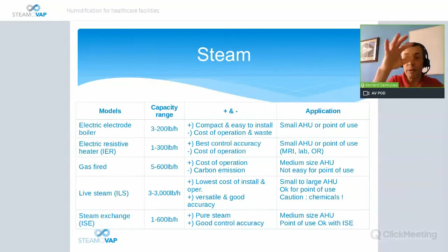But if you use a live steam humidifier at the point of use, it will be, let's say, one steam manifold, one ramp with a small valve, and then you can go to very low capacity, say 10, 30, 50 pounds. And then you can use it on the bigger air handling unit, feeding the whole hospital, at 3,000. That's a limit that we have placed, but you can go over 3,000 as long as you add pipes, nozzles and a larger valve. So it's probably the lowest cost of install and operation, very versatile, with very good accuracy. But caution, the chemicals have to be verified and controlled.